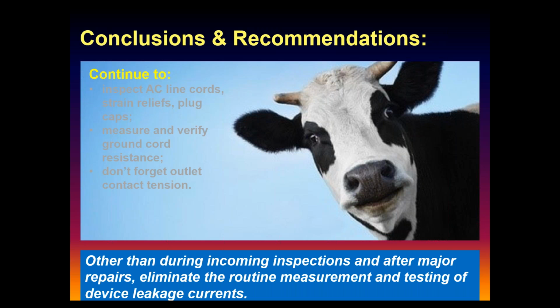It's a real funky concept - if you see 2 milliamps on the line isolation monitor, it's not a current that is flowing anywhere in the system. It's a predictive current that would flow if you had a line-to-ground fault. So it's a measure of how good the isolation is in the system, and the isolation is all based on parasitic capacitance between line 1 and ground, line 2 and ground. So if your isolation transformer is half a block away, you've got a whole lot of capacitance.